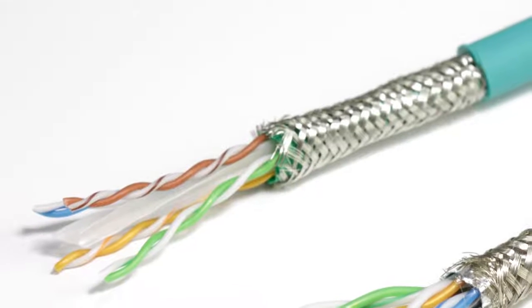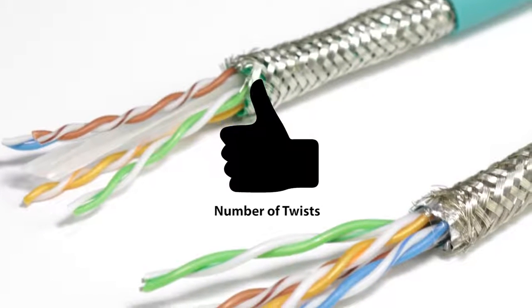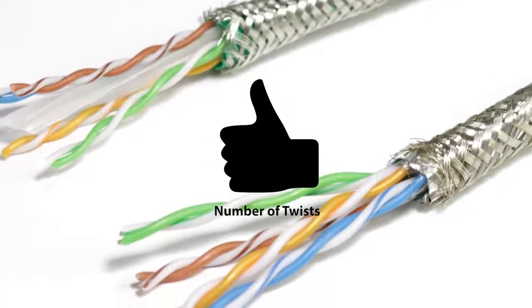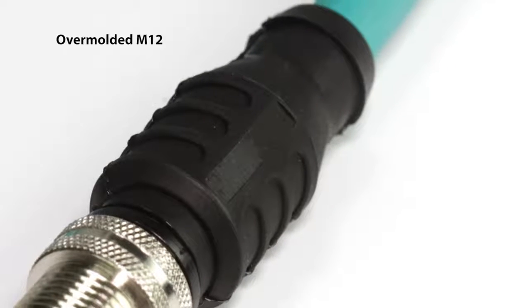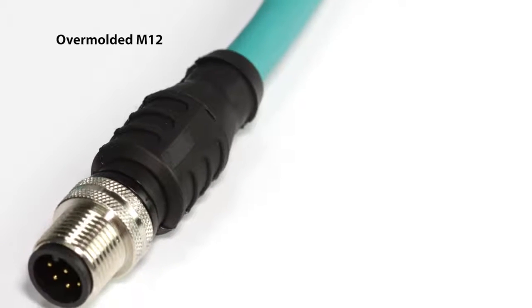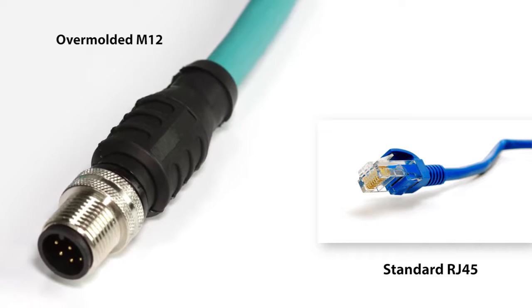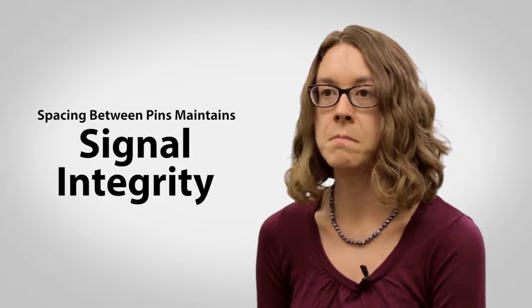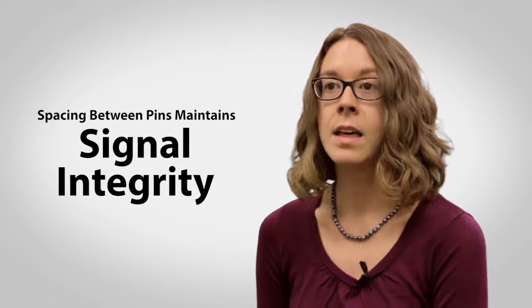For any Ethernet connector, the number of twists must remain at an acceptable level throughout the connector. An overmolded M12 is used for industrial Ethernet because it is considerably more robust and rugged than the RJ45, and the spacing between pins maintains signal integrity. This is what makes it ideal for the factory floor.